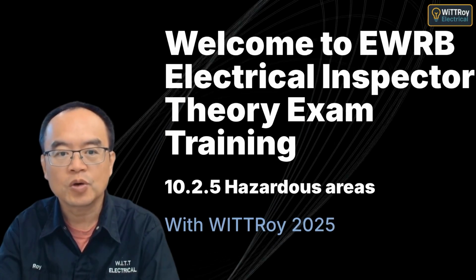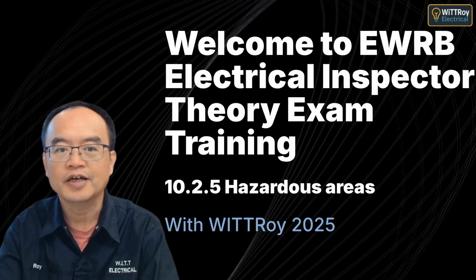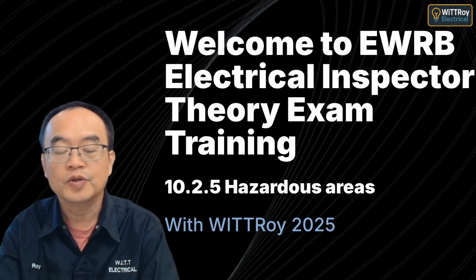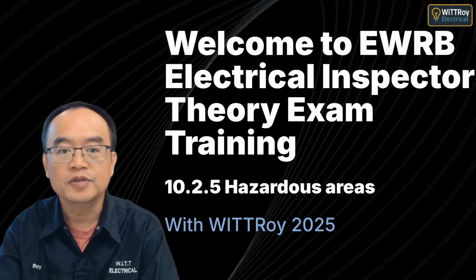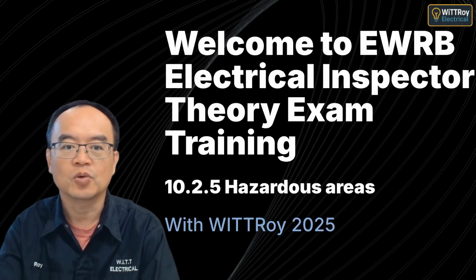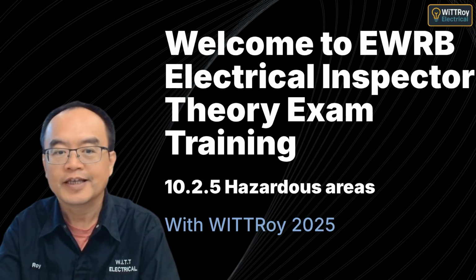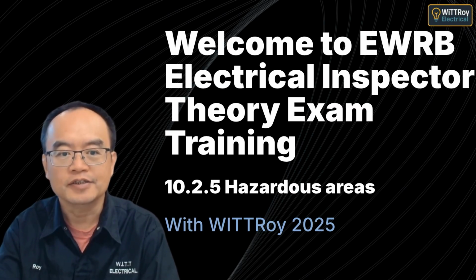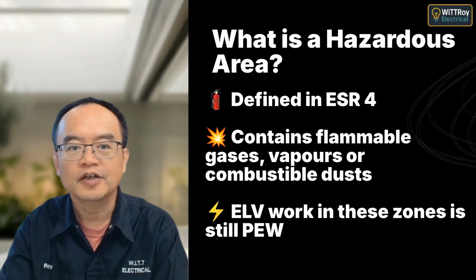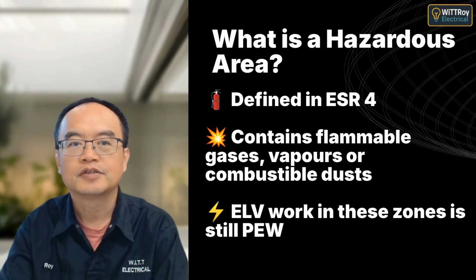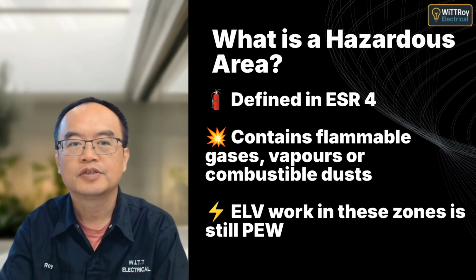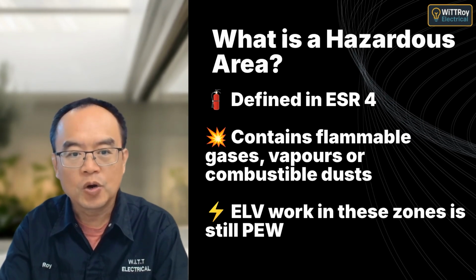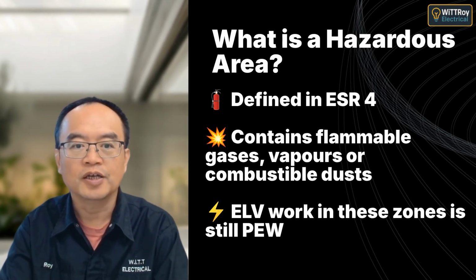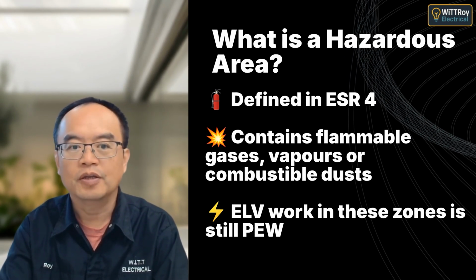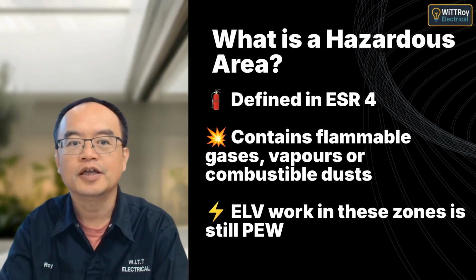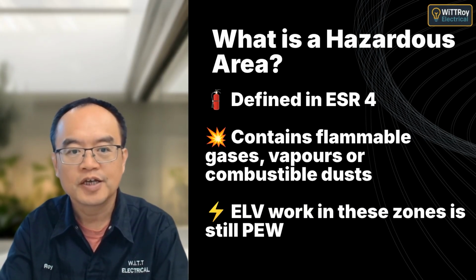In this short lesson, we're looking at 10.2.5 hazardous areas. This topic is critical because hazardous areas can involve explosive atmospheres, so electrical work here must follow strict safety rules under ESR and AS/NZS standards. A hazardous area is any location where flammable gases, vapors, or combustible dust may be present in quantities that could ignite. According to ESR, even work involving extra low voltage is still considered prescribed electrical work if it's in a hazardous area. That's because any spark could cause serious danger.